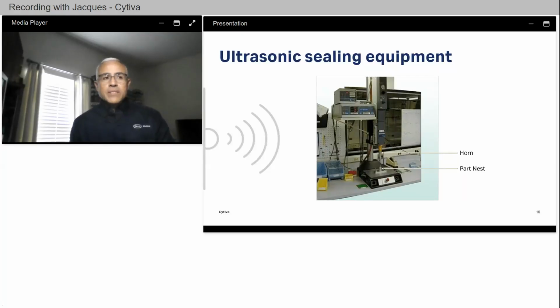The second sealing method in our discussion is ultrasonic sealing. Ultrasonic sealing equipment will also vary somewhat from model to model. The basic components that you will find in this equipment include an air cylinder, which applies the pressure, a converter or transducer, a booster, a horn, and a nest that holds the housing components in place during the processing.